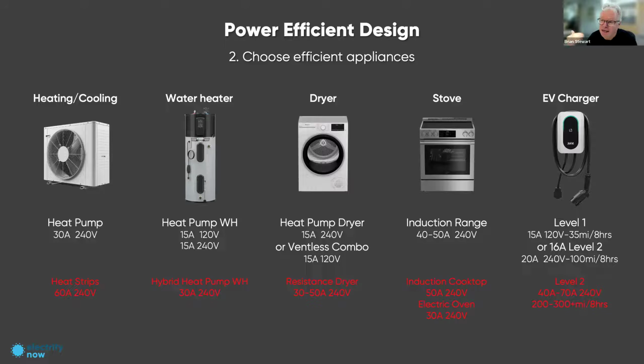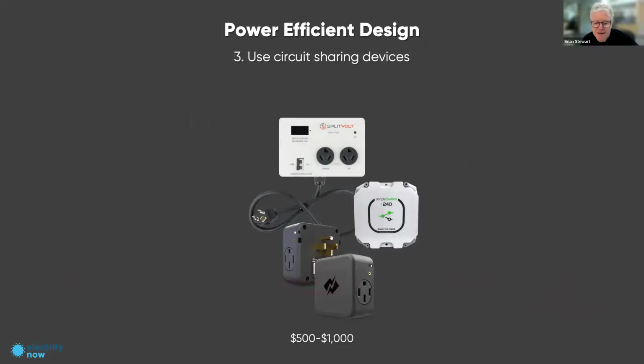The next level, which we've done before and seen others do, is installing a 16 amp level 2 charger—the lowest, slowest level of level 2 charging, but still amazing. Overnight you'll get about 100 miles of charge in a typical EV, using only a 20 amp circuit at 240 volts. If you can avoid the larger EV chargers, you'll save a lot of space on your panel for other things. It's all about balancing these choices and making a plan so you can stay within your amperage budget, so to speak, of 100 amps. That's one way to get there, and probably the center of this power-efficient design idea.